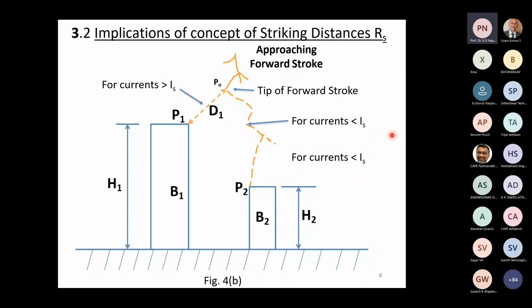Now let us see how we can apply it in practice for arriving at a protection system. Now in this figure, two buildings are shown, B1 and B2. Obviously, B1 is almost twice or even slightly more than B2. The lightning leader has approached down to point P0. The next distance we can calculate using the formula for step distance. So now, for a current I, let me say, it can reach P1 if the striking distance is equal to D1 or more.